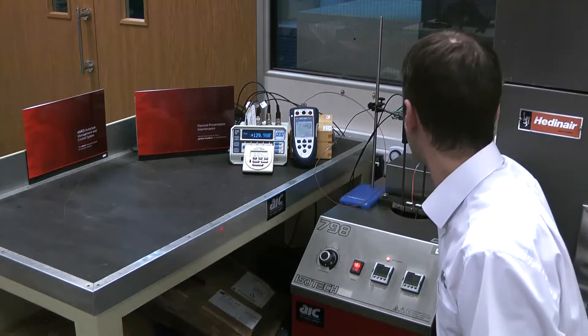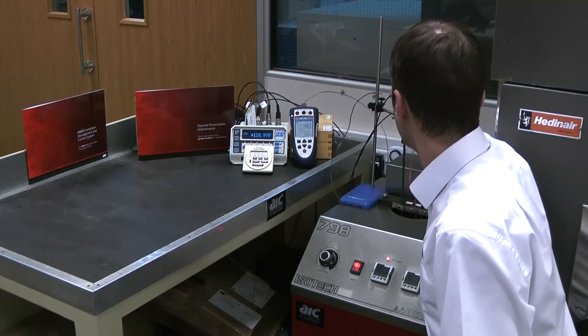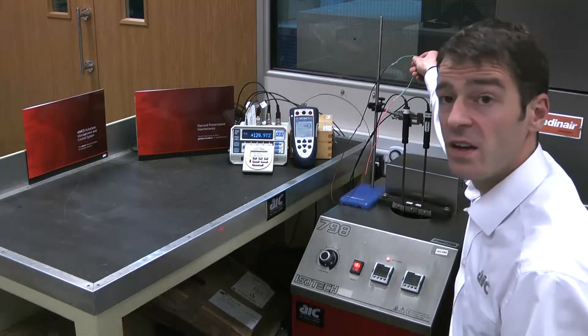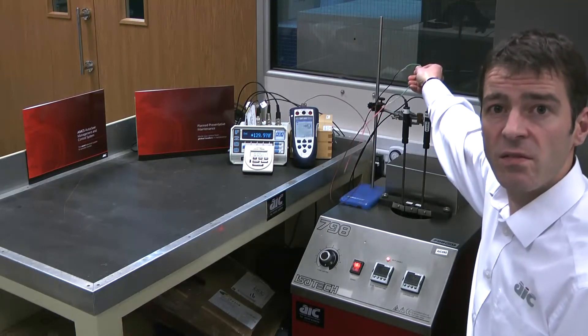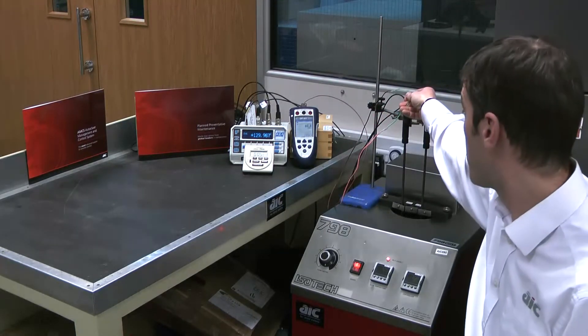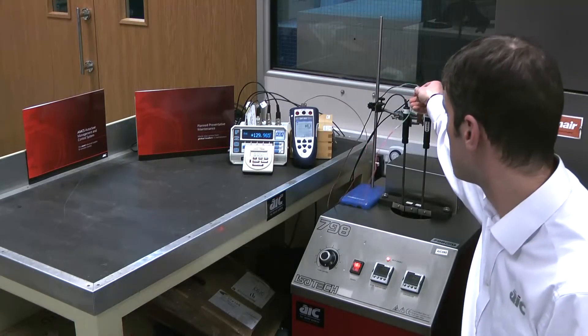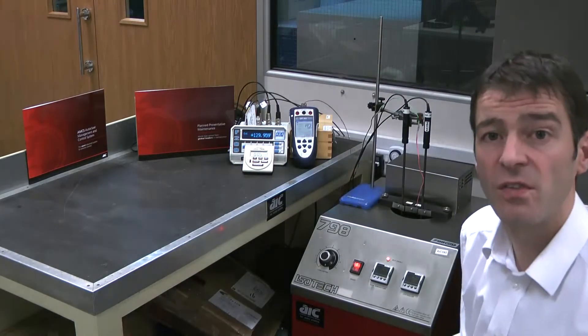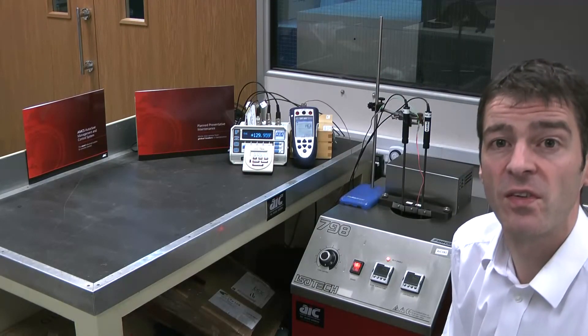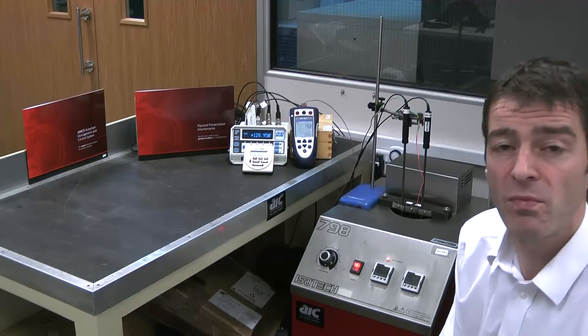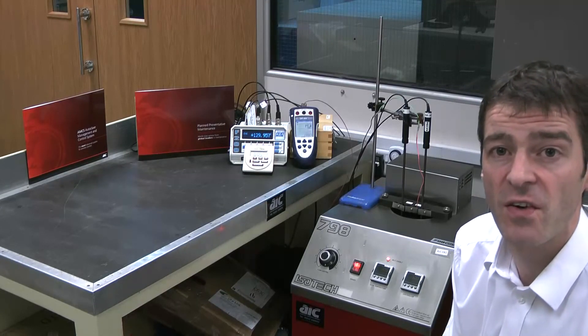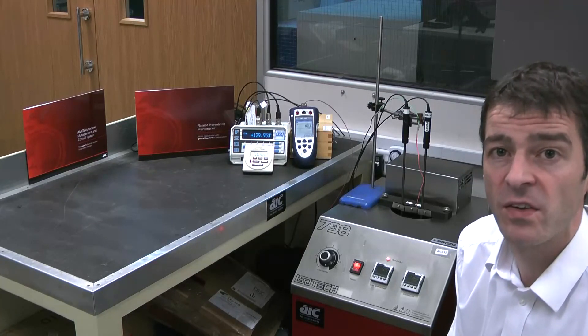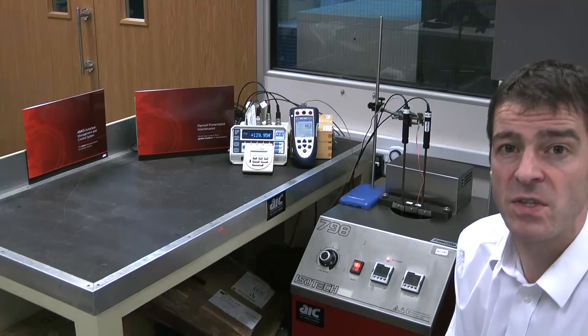And if I pull that all the way out, you can see that that's the end of it there, just the Type N thermocouple at the end where the junction is. But, as I think we've shown there, the junction is not terribly important when you're trying to get an accurate reading. What's most critical for trying to track down errors is to make sure that you know what the character of the cable is where there is a temperature gradient.